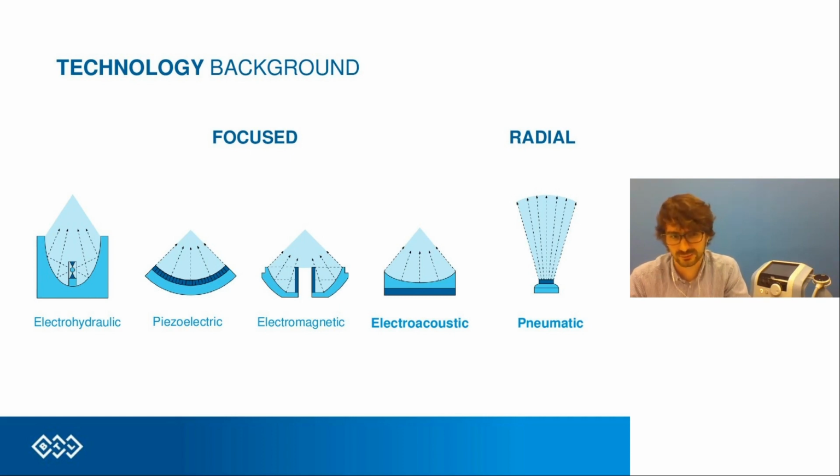And basically we managed. We wanted to have comparable clinical parameters as with the electromagnetic or electrohydraulic devices, but we wanted to have a very high lifespan such as piezoelectric devices. We achieved this by putting together a bunch of things, and we got inspired by all the previous technology. So currently we are using this electroacoustic lens system, which is the brighter blue part of this picture, and underneath we have basically one single piezoelectric crystal.